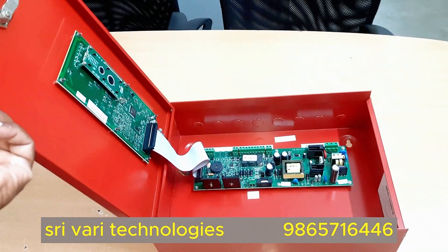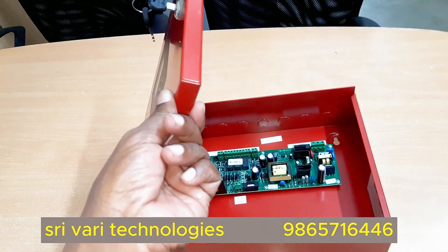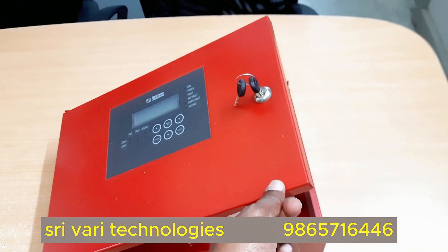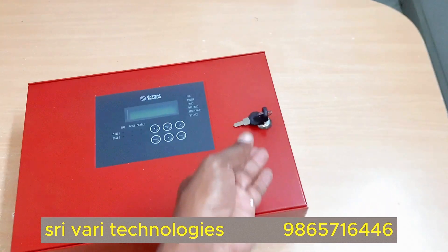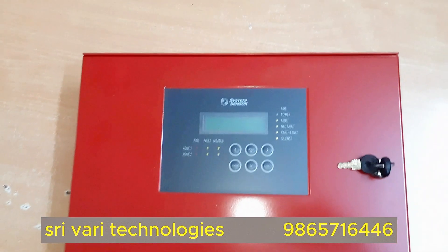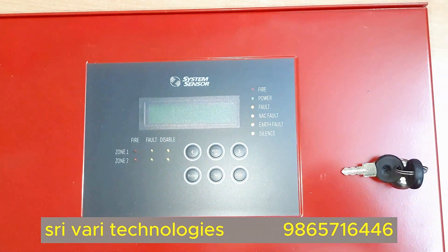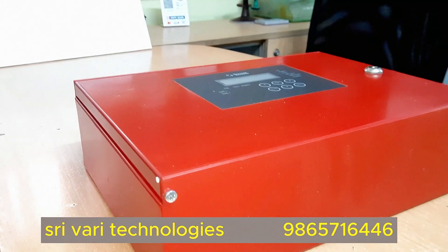Panel keys include silence buzzer, reset, navigation keys — left, right, down — menu and OK. Lamp test and walk test are available. Standby power 24V DC, using two 12V 7Ah lead-acid batteries. Certification: CE and LVD. The event log can store up to 1,200 events. Earth fault monitoring is also available.